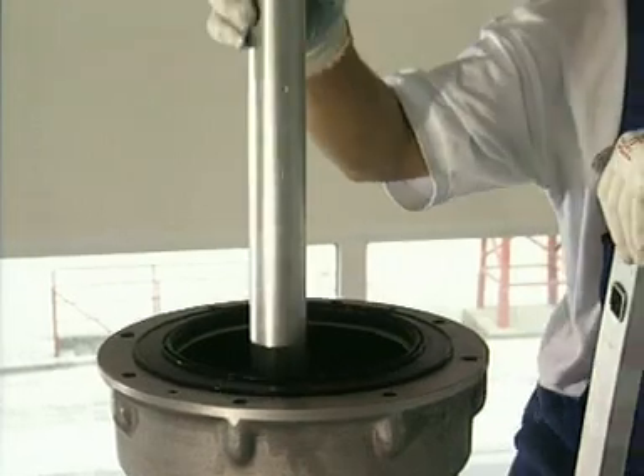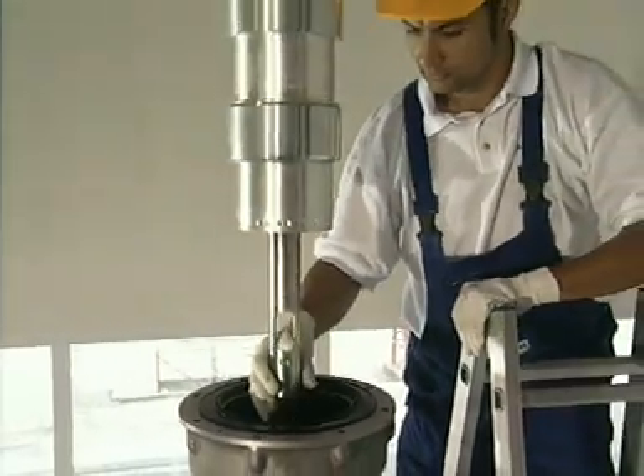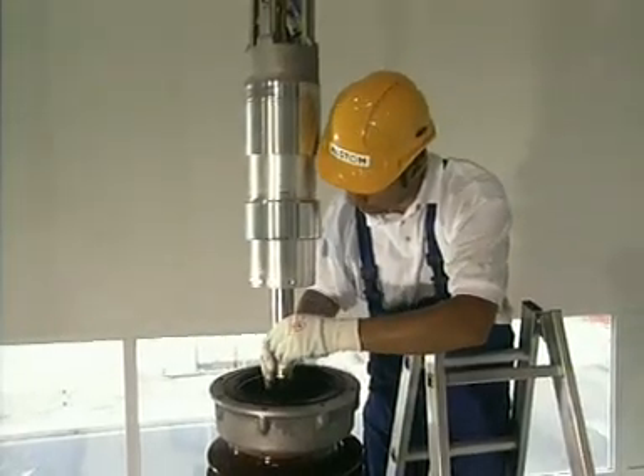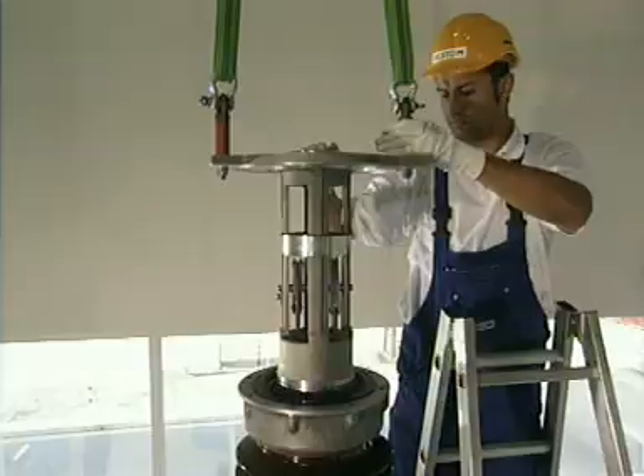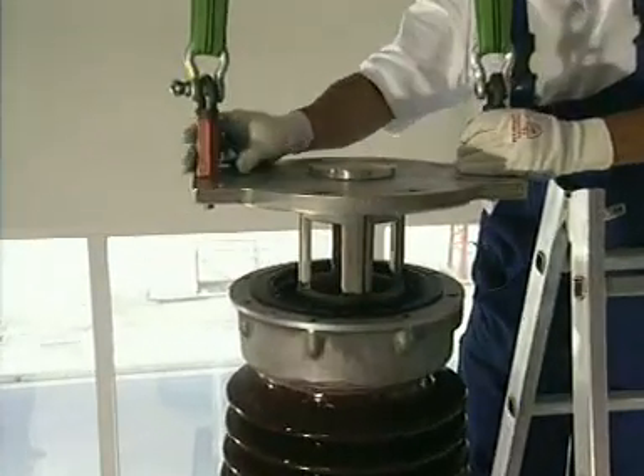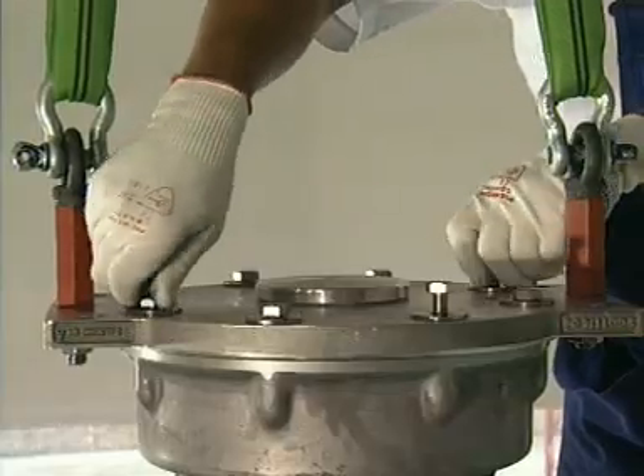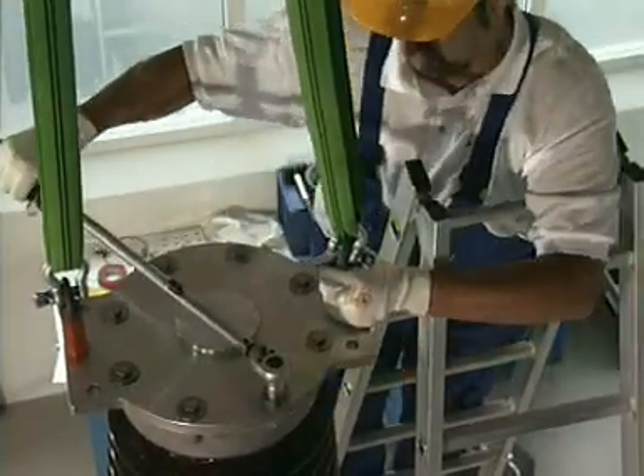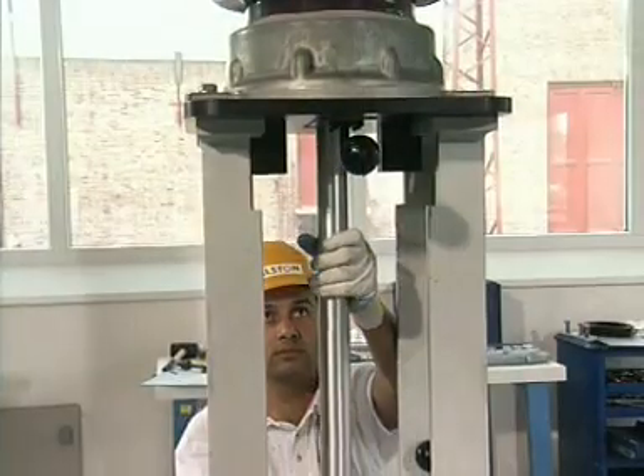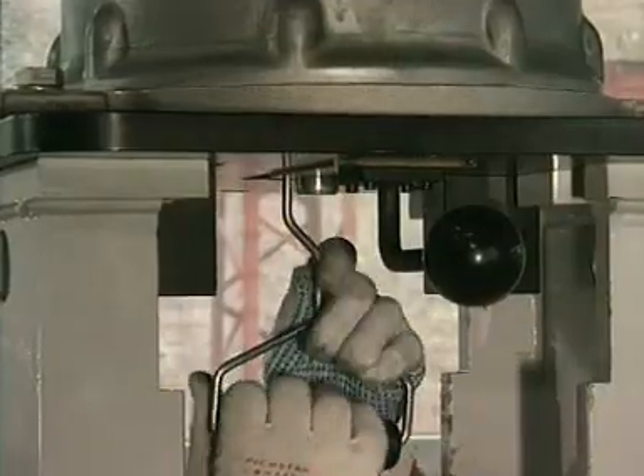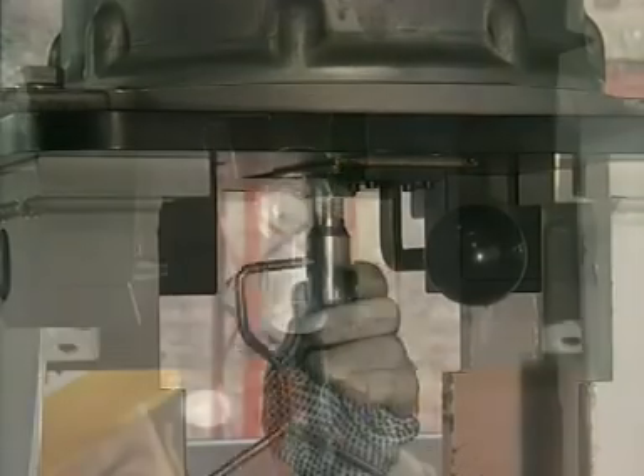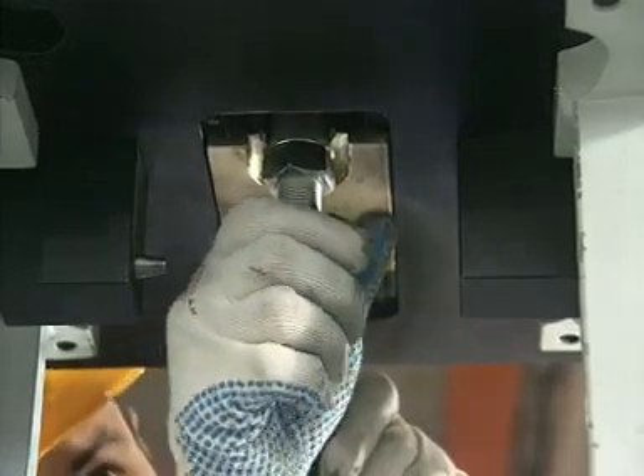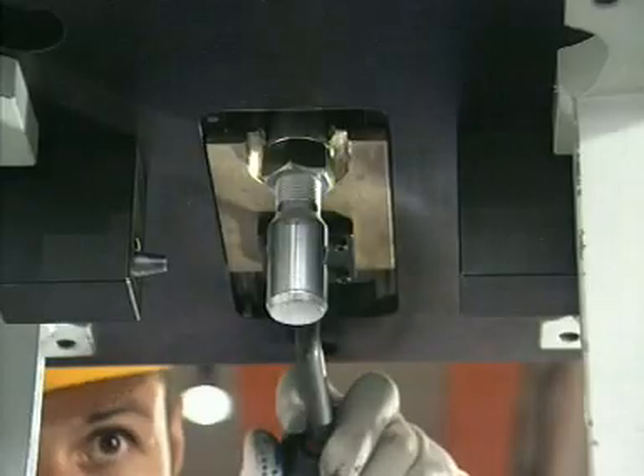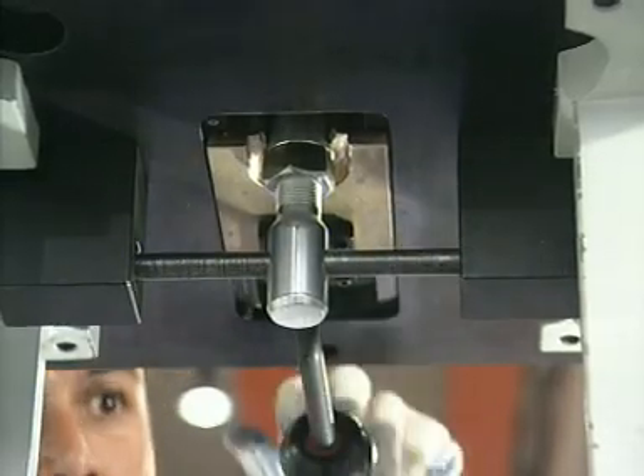Push the centering device on the new double motion unit. Lower it into the chamber porcelain. Insert the screws in the upper flange and tighten them using a torque wrench. Pull off the centering device and move the double motion unit to the open position using a hook. Fix the linkage in position using the mounting device, adjust it as specified in the operating instructions and lock it.